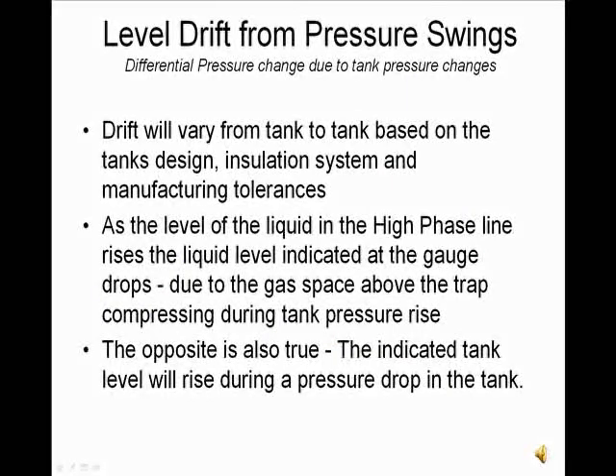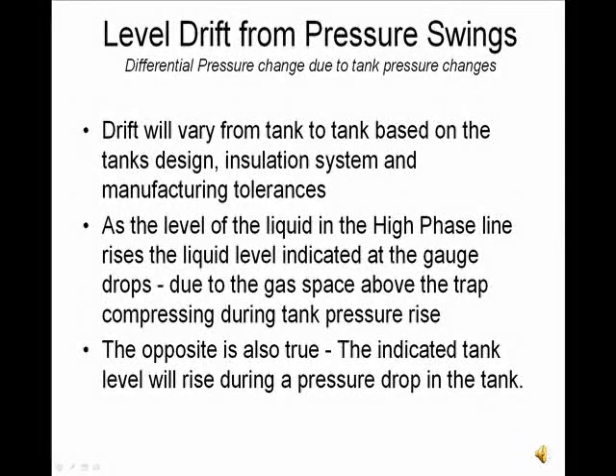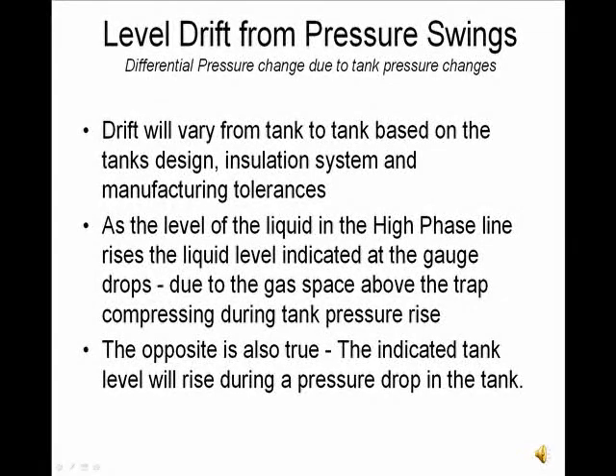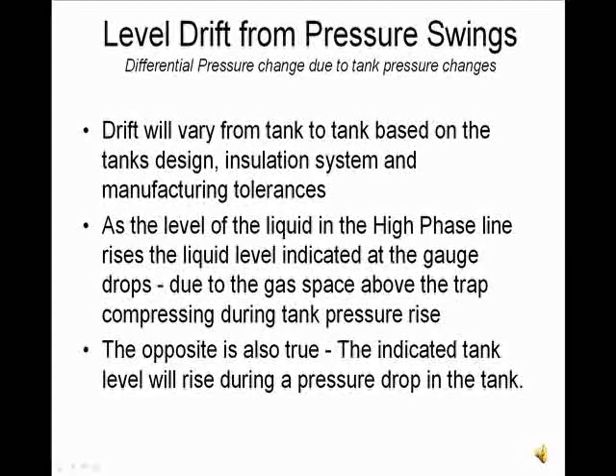The next series of slides will explain the differential pressure drift and the corresponding level drift due to a pressure swing. This drift will vary from tank to tank based on the tank's design, insulation system, and manufacturing tolerances. Very simply, as the level of the liquid in the high phase line rises, the liquid level indicated at the gauge drops. This is due to the gas space above the trap compressing during tank pressure rise. The opposite is also true — the indicated tank level will rise during a pressure drop in the tank.